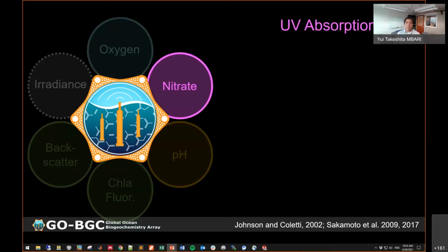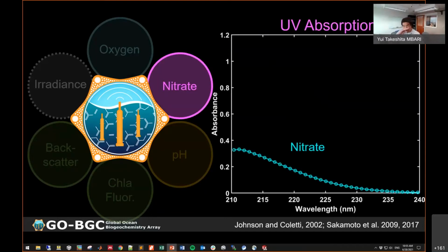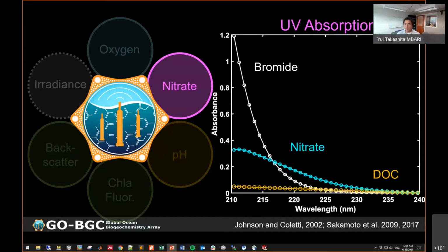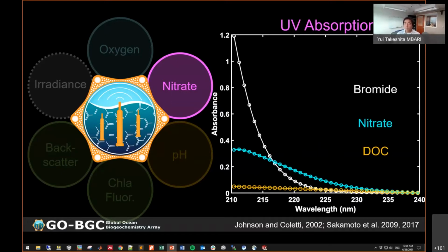Nitrate sensors measure nitrate using UV absorption. Nitrate absorbs in the deep UV. This is the absorption spectra from 210 to 240 nanometers. But the complication is that other compounds in seawater absorb in the same range as well, namely bromide, and also dissolved organic carbon, which we parameterize as a linear fit. So when you actually measure the absorbance of seawater in this range, it's a sum of these three components.